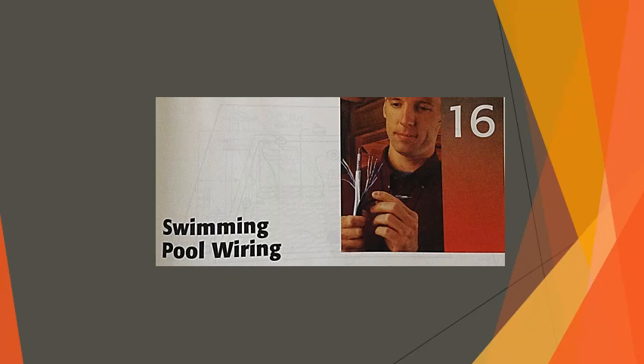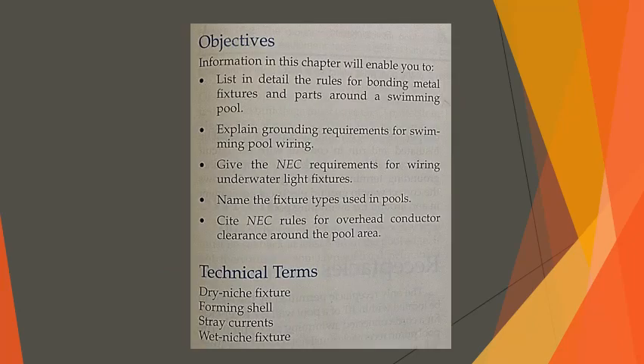Moving on to the last chapter of this section, swimming pool wiring. Some of the objectives in this chapter are to list in detail the rules for bonding metal fixtures and parts around a swimming pool, explain grounding requirements for swimming pool wiring, give the NEC requirements for wiring underwater light fixtures, name the fixture types used in pools, and cite the NEC rules for overhead conductor clearance around the pool area. Technical terms used are dry niche fixture, forming shell, stray currents, and wet niche fixture.